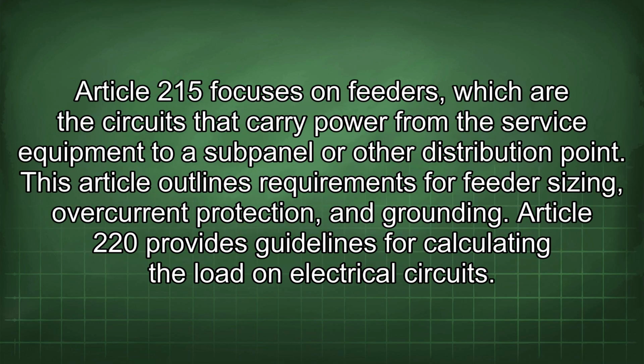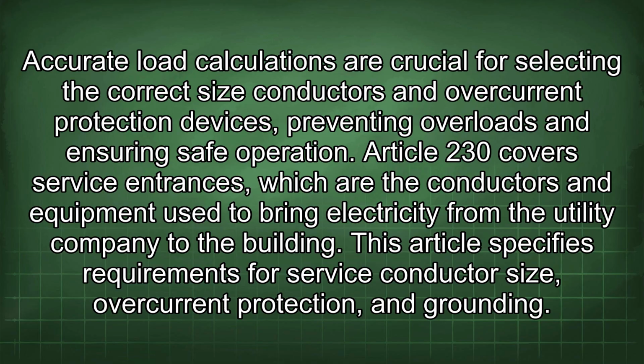Article 215 focuses on feeders, which are the circuits that carry power from the service equipment to a subpanel or other distribution point. This article outlines requirements for feeder sizing, overcurrent protection, and grounding. Article 220 provides guidelines for calculating the load on the electrical circuits. Accurate load calculations are crucial for selecting the correct size conductors and overcurrent protection devices, preventing overloads and ensuring safe operation. Article 230 covers service entrances, which are the conductors and equipment used to bring electricity from the utility company to the building. This article specifies requirements for service conductor size, overcurrent protection, and grounding.